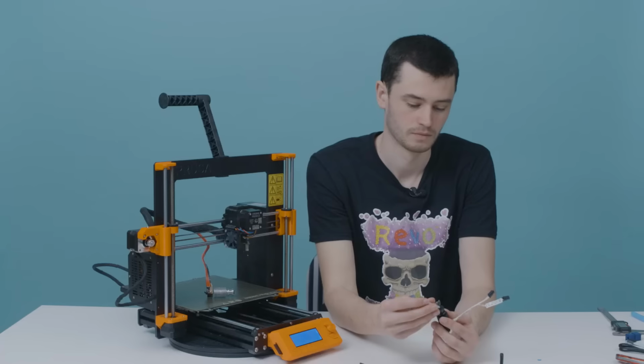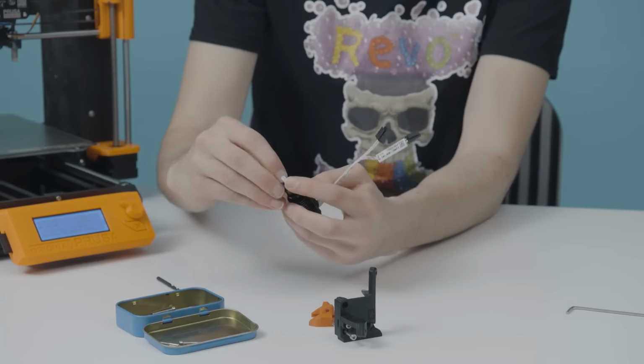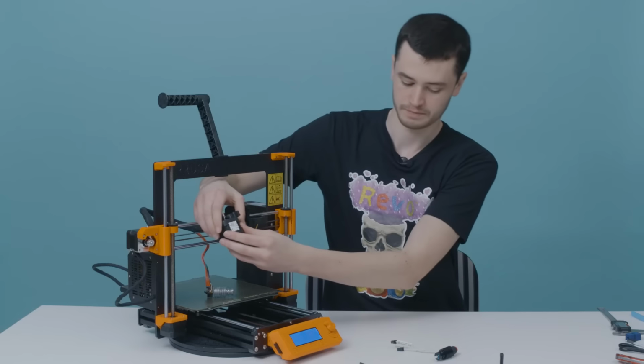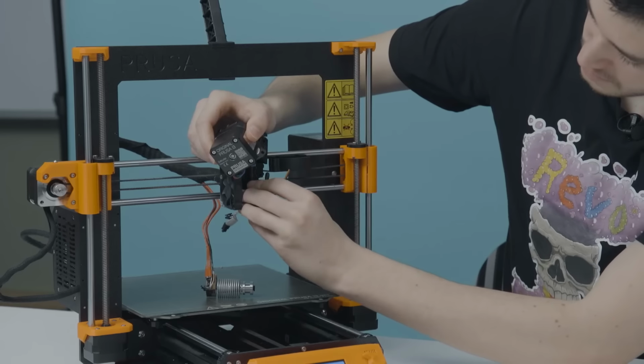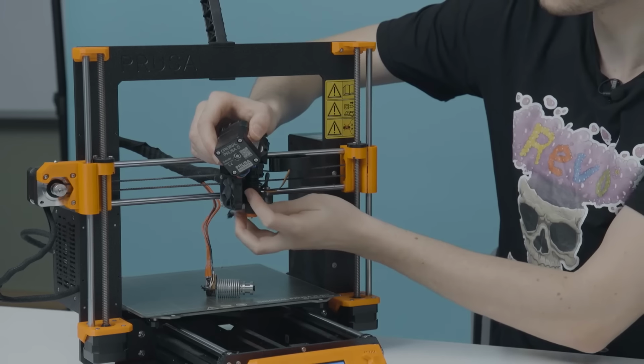Put the tube into Revo 6 and remember to reattach the collet clip. Pull the motor away from the casing and slot the Revo 6 into place. It can be a little fiddly to get the PTFE tube in the right place.